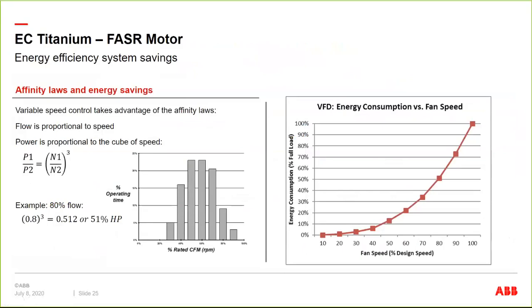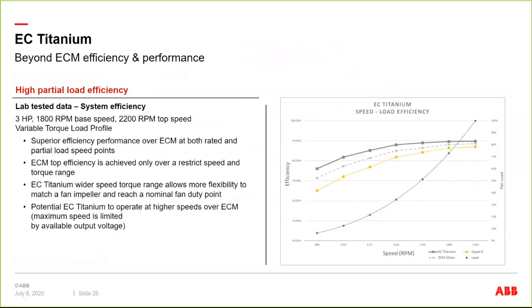Most of them run on that bell-shaped curve that you see in the gray lines there. So they're running the majority of their time at 80, 60% speed and at partial load conditions, because it's the cube rule of speed and load. So, if you're at 80% speed, you're only at 50% load. So what you really have to look at is, well, what is my motor efficiency if I'm operating at those reduced speed and reduced load points?